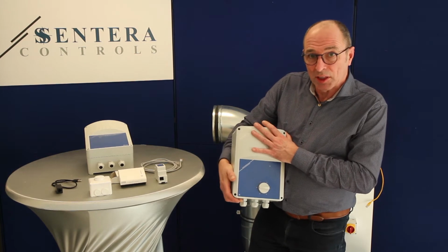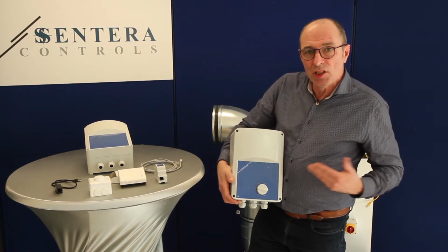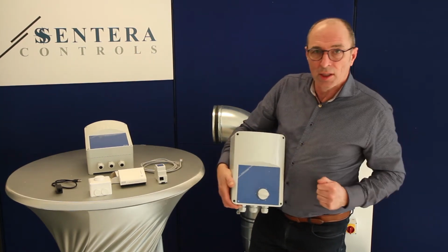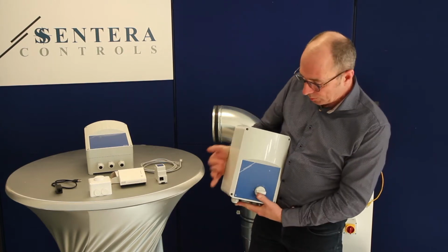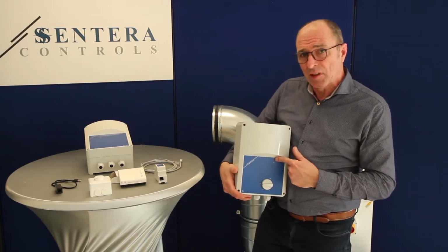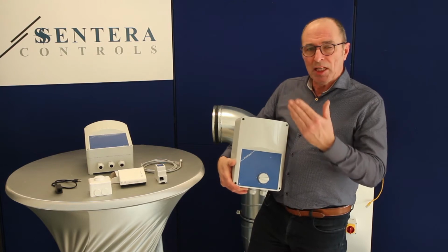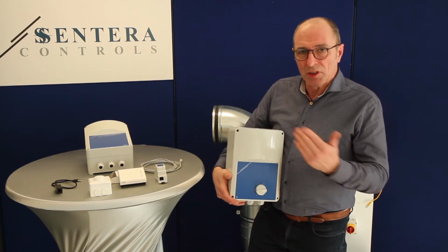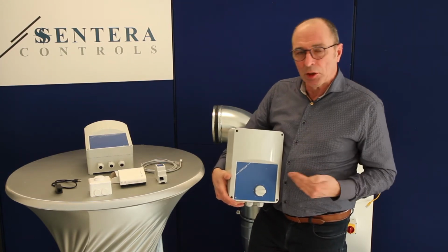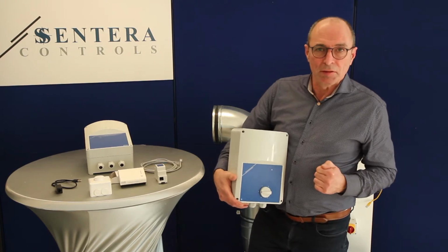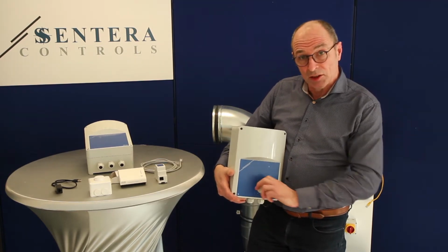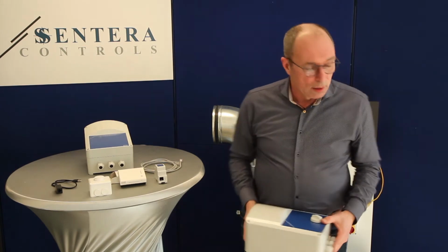Thanks to the built-in transformer, this is done with a perfect sinus-shaped signal as it comes from the mains. It is only the amplitude of the signal that you're going to change. So instead of 230 volts, the same beautiful sine wave shape comes out of the unit with an amplitude of 80, 110, 170 volts and so on. And this depends on the position of the rotary switch.